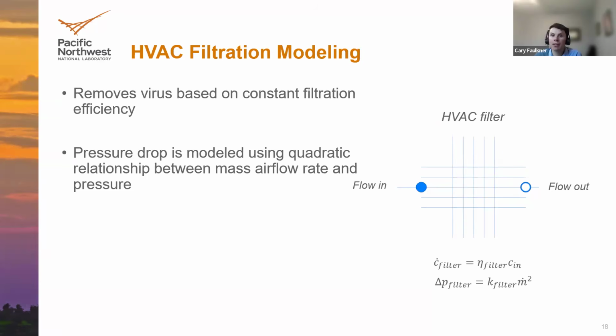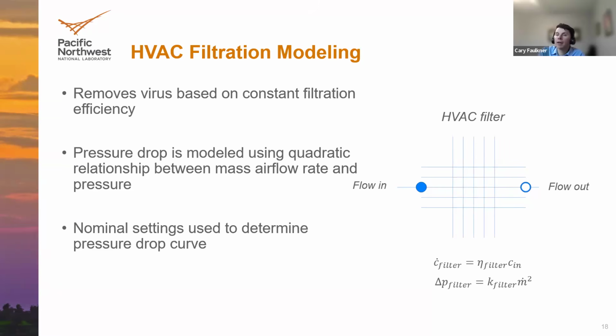And so we want to be able to capture this pressure drop that is imposed on the HVAC system from the HVAC filter. And we describe this using an assumed quadratic relationship between the mass airflow rate and pressure. And then we define some nominal settings to create a pressure drop curve as a function of mass airflow rate. And those nominal settings are going to be different for different filters and define the differences in the pressure drop curves for different filters.